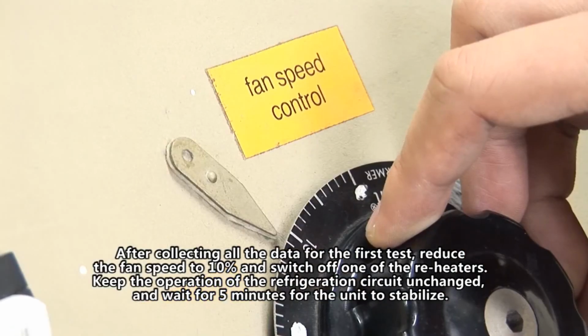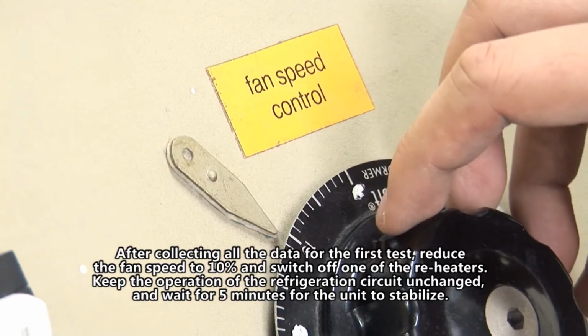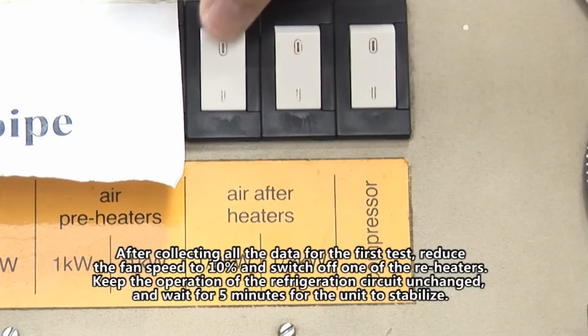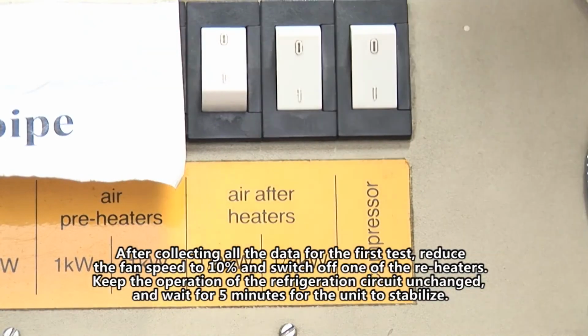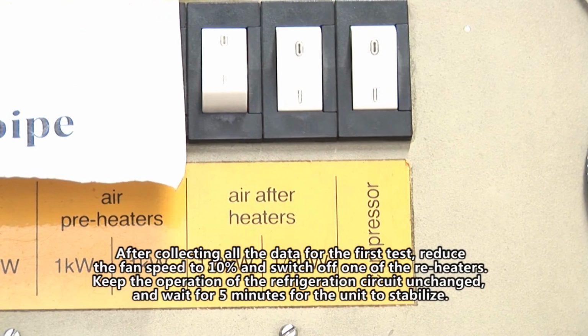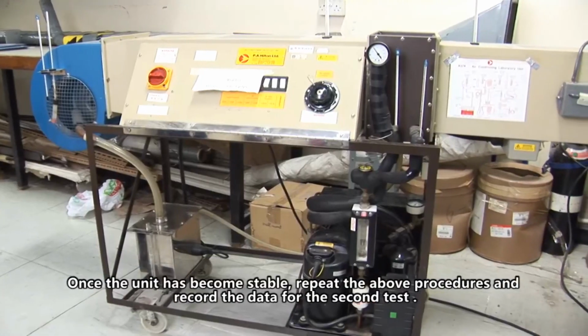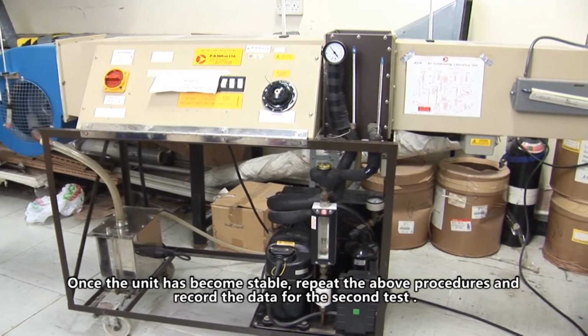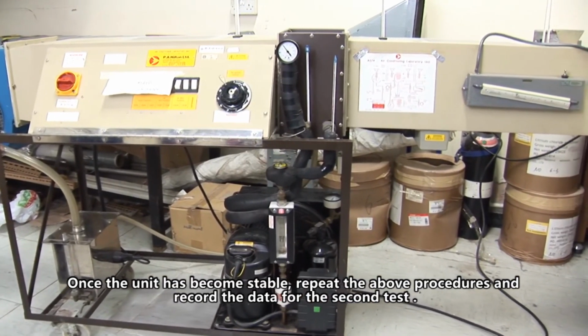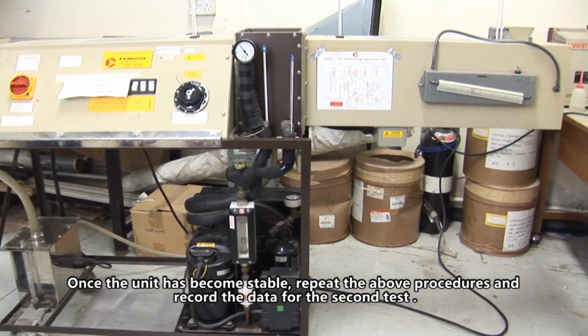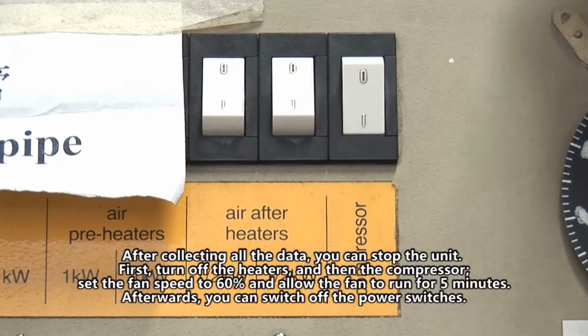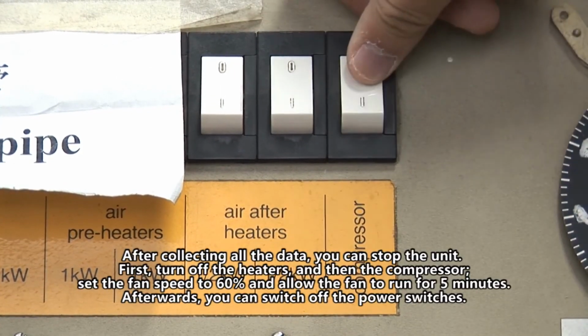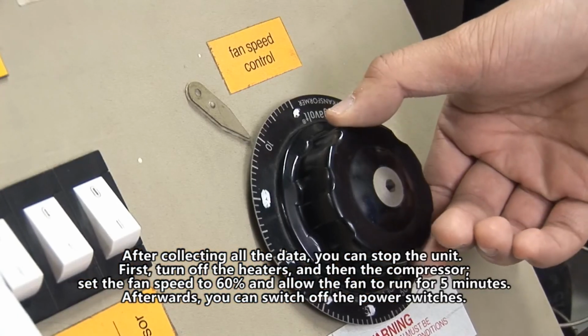After collecting all the data for the first test, reduce the fan speed to 10% and switch off one of the reheaters. Keep the operation of the refrigeration circuit unchanged and wait for 5 minutes for the unit to stabilize. Once the unit has become stable, repeat the above procedures and record the data for the second test.